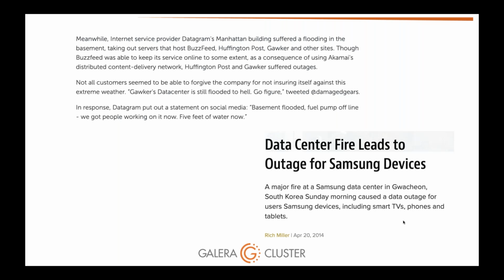Also, floods can happen. If you read the top left-hand corner, this is actually Hurricane Sandy affecting New York, where at least 8 data centers were down, struggling with connectivity because it was starting to flood inland of downtown Manhattan. Flooding was basically submerging and destroying diesel pumps and preventing fuel from being pumped to the generators at a higher level.